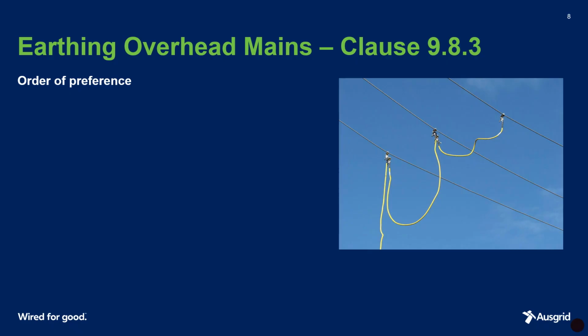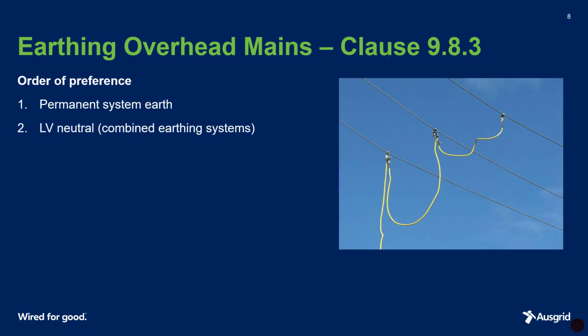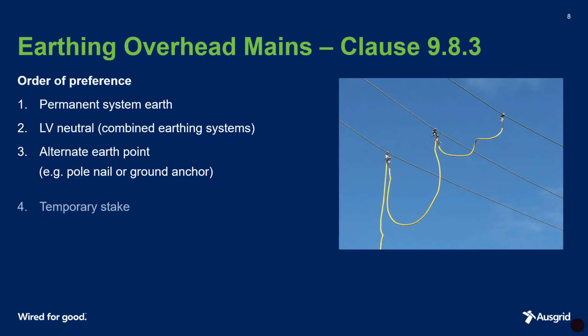The order of preference for the means of connecting overhead mains and apparatus to the general mass of earth has been included in Clause 9.8.3. The order of preference is: firstly, a permanent system earth. Secondly, where the surrounding distribution substations utilise a combined earthing system, a low voltage neutral conductor. This option does not apply to the earthing of subtransmission mains. Thirdly, an alternate earth connection such as a pole nail or ground anchor. And lastly, a temporary earth stake.